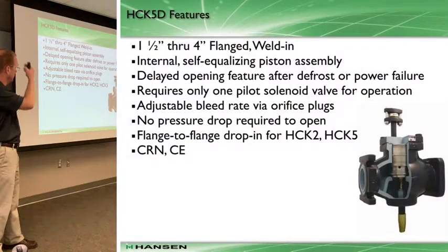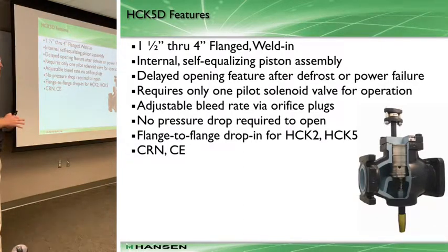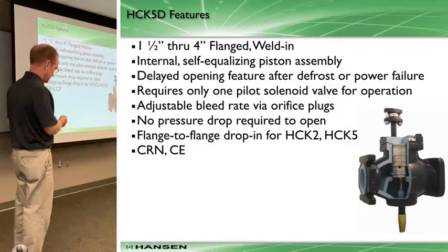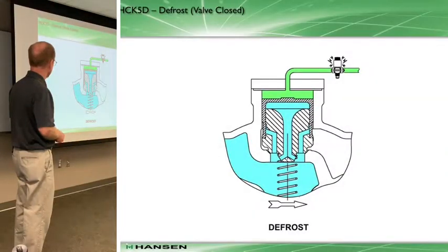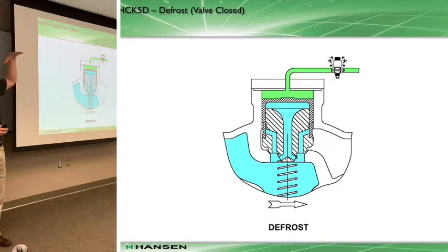There's another innovation called the HCK5D - D stands for dual or dual-position valve. It's a two-step valve, kind of like the HS4Ds that Phil talked about earlier. Within this one valve there are actually two different stages. It's the same basic concept as an HCK2 with a simple piston, but now you have two pistons - an upper and a lower piston.